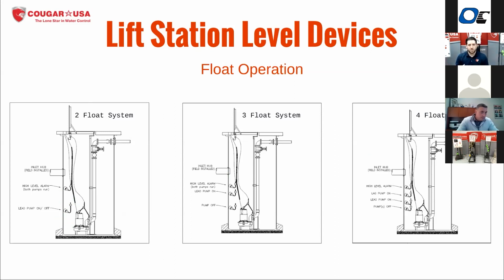Okay. So if you don't have a very big pit or you need to create a longer pumping range, then going with a two float system like this is maybe not the best design because you are limited to turning on and off the pump with a single float switch. Okay. But this is a very simple way to do it.